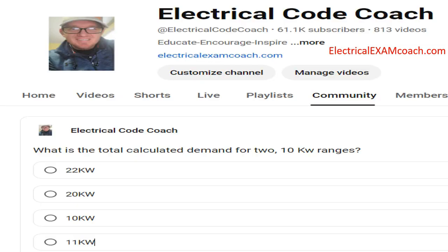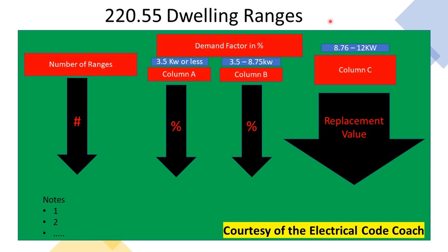What is the total calculated demand for a service where there are two 10 kW ranges in a residential setting? The correct answer is 11 kW. The answer to this question — thankfully — requires no calculation at all. We get to use one of my favorite tables in the NEC: Table 220.55. This is a more complex subject, and if you head over to electricalcodecoach.com you can learn all about the nuances of the three different columns, how to apply them, absolutely for free — just click on the free version and go to about week four to find the full lesson. But today let's answer this individual question.